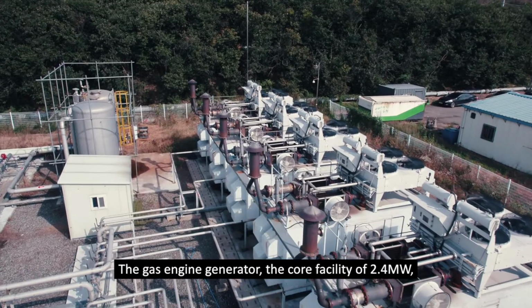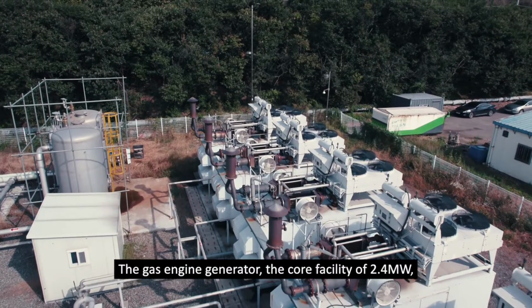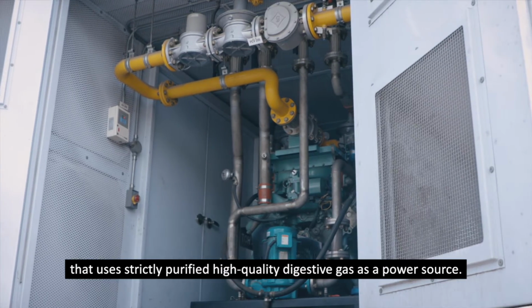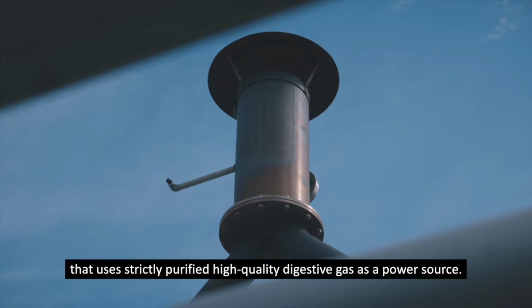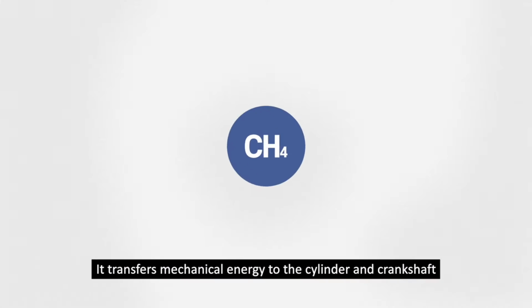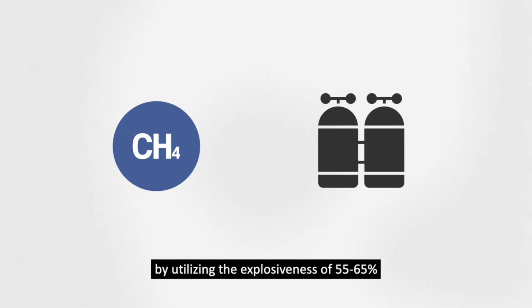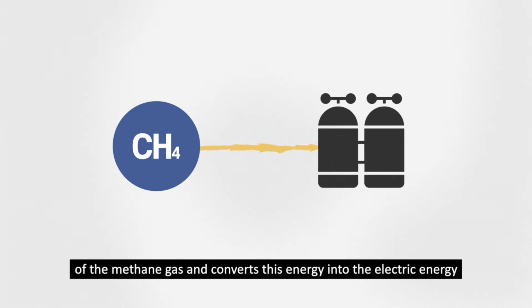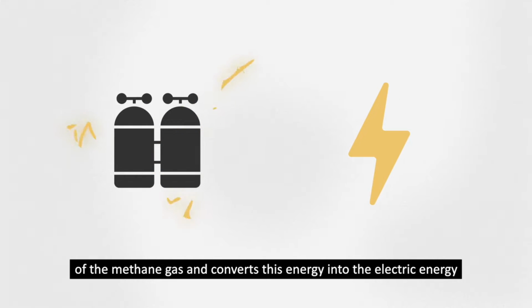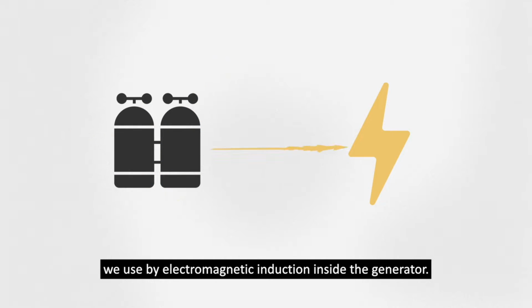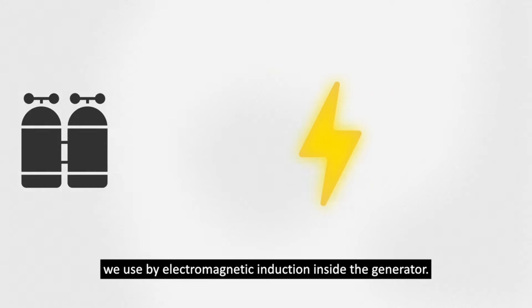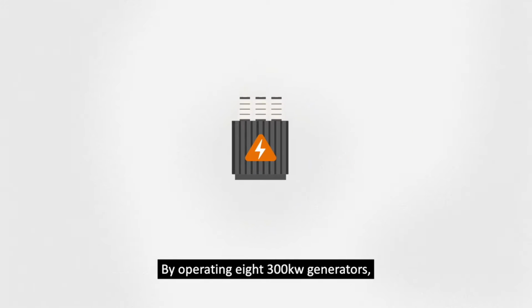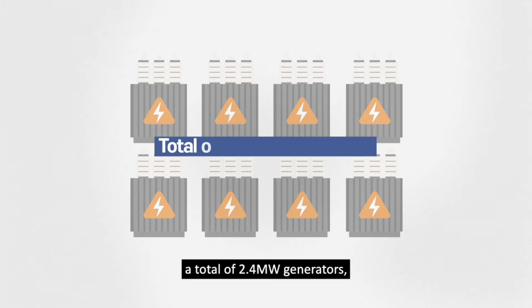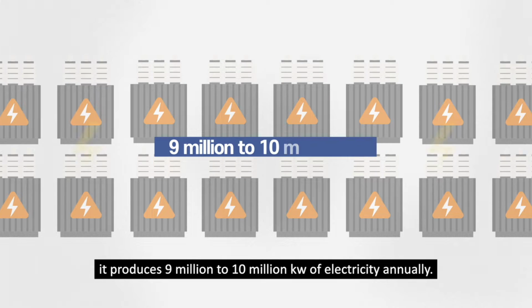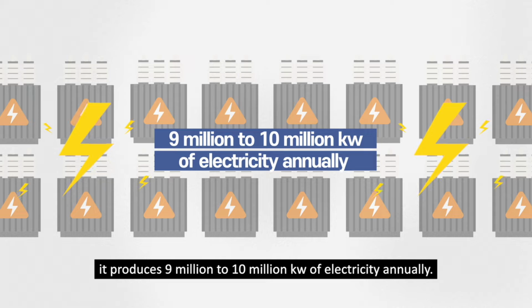The gas engine generator, the core facility of 2.4 megawatts, is a small and medium-sized generator that uses strictly purified high-quality digestive gas as a power source. It transfers mechanical energy to the cylinder and crankshaft by utilizing the explosiveness of 55 to 65% of the methane gas and converts this energy into the electric energy we use by the electromagnetic induction inside the generator. By operating 8 300 kilowatt generators, a total of 2.4 megawatt generators, it produces 9 million to 10 million kilowatts of electricity annually.